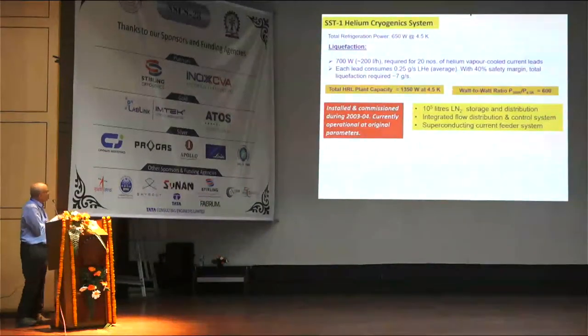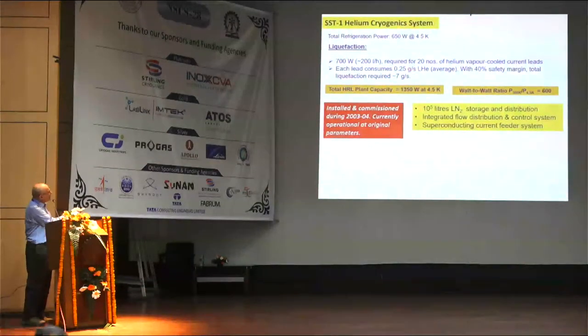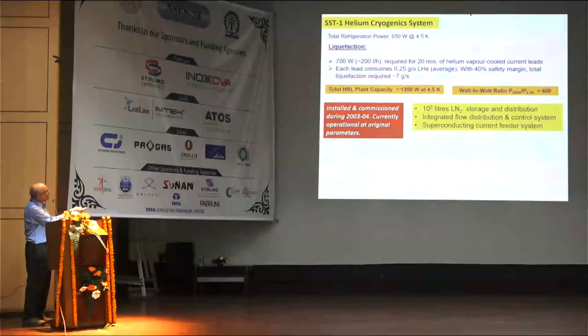Coming to the SST1 helium cryogenic system, the total refrigeration power required is 650 watts at 4.5 Kelvin. Apart from that, we have a liquefaction requirement because we have current leads for feeding the superconducting magnets. We need something like 200 liters per hour because there are 20 helium vapor-cooled current leads, each needing around 0.25 grams per second liquid helium. With the safety margin, we require about 7 grams per second. So the total helium plant capacity is around 1350 watts at 4.5 Kelvin.